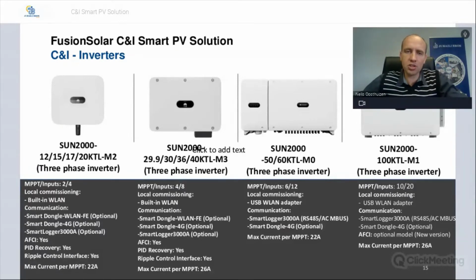Then if we go to the largest section of the C&I solutions that's available, the first inverter range in the largest section would be the 50 or the 60 kTL. It's still M0, meaning it's the first division or the first derivative of this specific inverter. Difference between this one and the previous one is it's got 6 MPPTs, meaning 12 strings can be connected to it. Local commissioning will be done via USB WLAN, and then the communication on this inverter is either through the smart logger or a smart dongle 4G. Maximum current per MPPT, 22 amps.